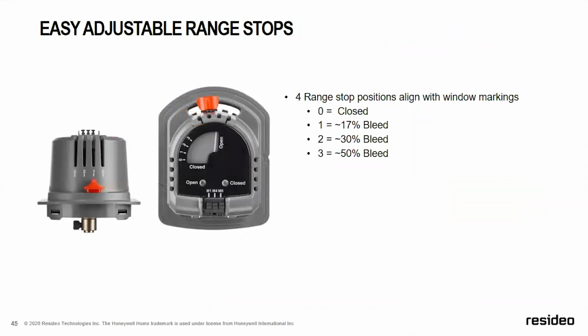This is our range stops. 0 is fully closed. 1 is 17%. 2 is 30. 3 is 50. I would typically never go into 3. The usage for range stops is if you have a small zone, let's say you have a 3-zone system. You've got 1 small zone and 2 large zones. So I've got a 20x8, a 24x8, and a 12x8. On my 24x8, I can put a bleed rate of 1 or 2. When my smallest zone opens, I'm still going to get some bleed rate, which gets me lower static pressure on startup, which keeps me from hitting my limit on an ECM motor. More about that when we get into the bypass.